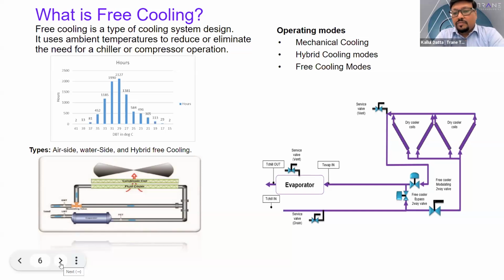Free cooling isn't literally free because it requires a lot of capital investment to own, but the payback period can be much more rapid depending upon the range of the ambient temperature. It means that depending on the climatic conditions in which you select those chillers, and depending on the application and the chilled water leaving temperature. For example, free cooling may not be applicable anywhere and everywhere. If you talk about the healthcare or pharmaceutical segment, where the process chilled water requirement comes close to 4 to 5 degrees centigrade, the free cooling payback period would be very, very high. So free cooling may not be applicable in those cases. But if you talk about the DC space, where today's modern servers are able to withstand very high temperatures, chillers can be designed at a very elevated leaving water temperature, and the payback period in such applications could be even less than a year.